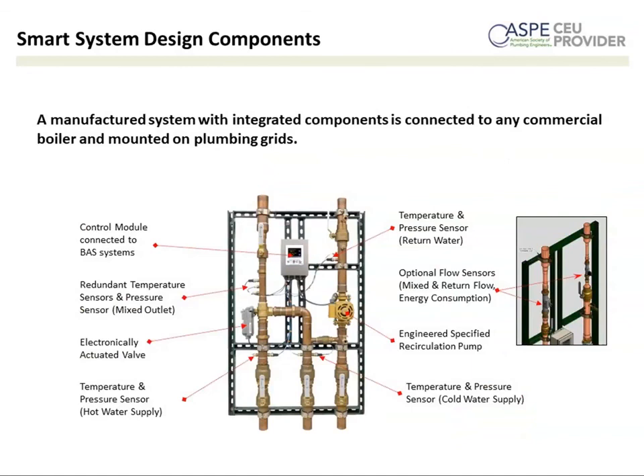So this is a typical system that you see here, and it looks like there's a lot of components there, but what you see here is a fully assembled, tested station. So this has already been properly sized. The pump has been selected by the engineer, or if we can, we or other manufacturers can select the pump based on the requirements needed. But this system is custom designed. It's mounted on racks, and so it makes it very easy for the installer to put into the building and then to set up.